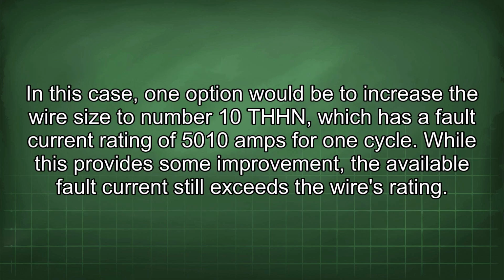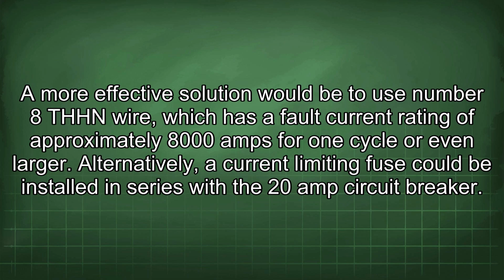In this case, one option would be to increase the wire size to number 10 THHN, which has a fault current rating of 5010 amps for one cycle. While this provides some improvement, the available fault current still exceeds the wire's rating. A more effective solution would be to use number 8 THHN wire, which has a fault current rating of approximately 8000 amps for one cycle or even larger.